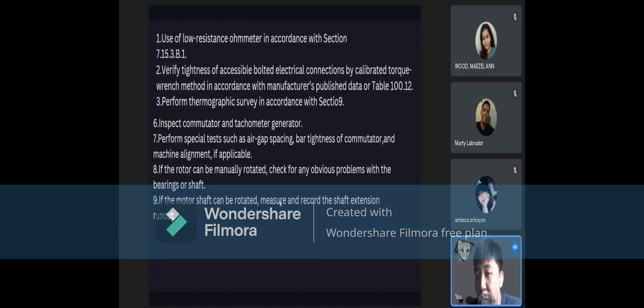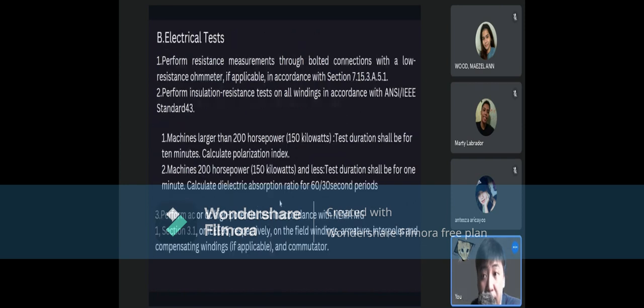6. Inspect commutator and tachometer generator. 7. Perform special tests such as air gap spacing, bar tightness of commutator, and machine alignment if applicable. 8. If the rotor can be manually rotated, check for any obvious problems with the bearings or shaft. 9. If motor shaft can be rotated, measure and record the shaft extension runout. B. Electrical tests. 1.